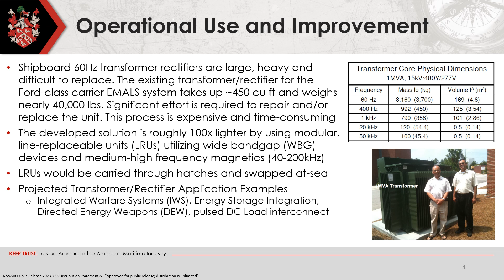Each cell rectifies from AC to DC, including galvanic isolation, through the approximately 100 kHz transformer design. Each cell is estimated to achieve up to 15 kilowatts at nominally 1 kilovolt. One of the design highlights is a minimized thermal load by device packaging, board tracing, and transformer design. While accounting for mission duty cycle requirements, reducing thermal management demands can optimize for system-level power density gains. The design is also set up for operational availability due to the ability to swap LRUs at sea when needed in a plug-and-play manner.